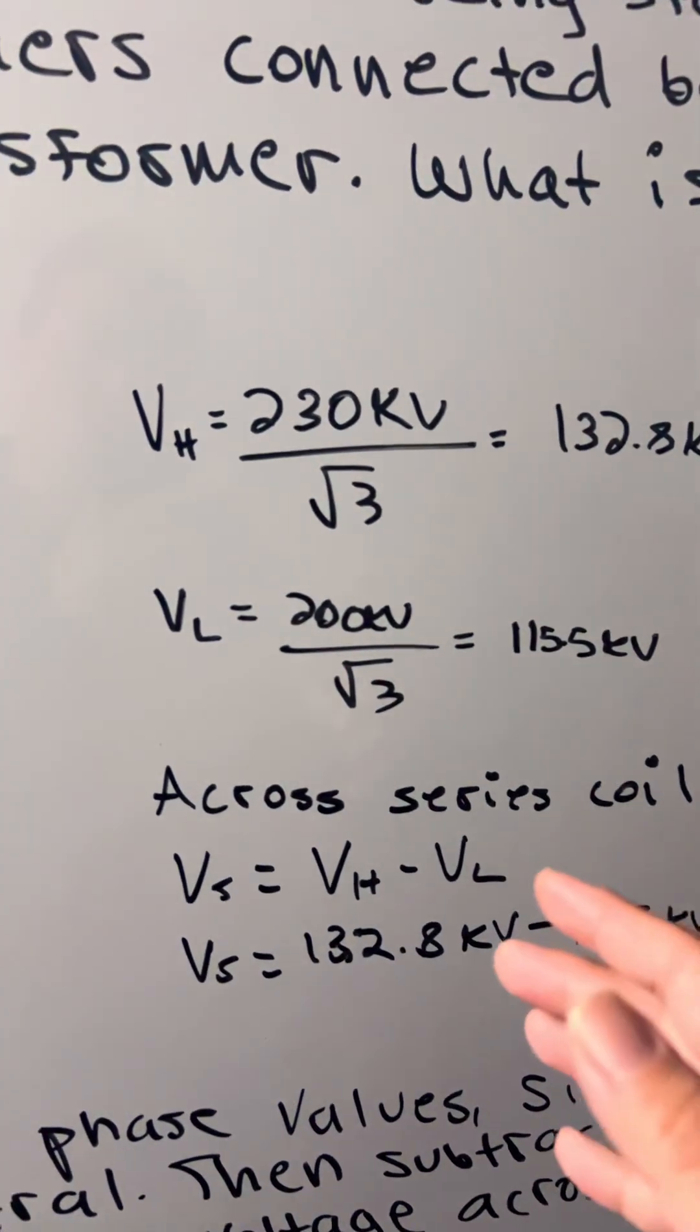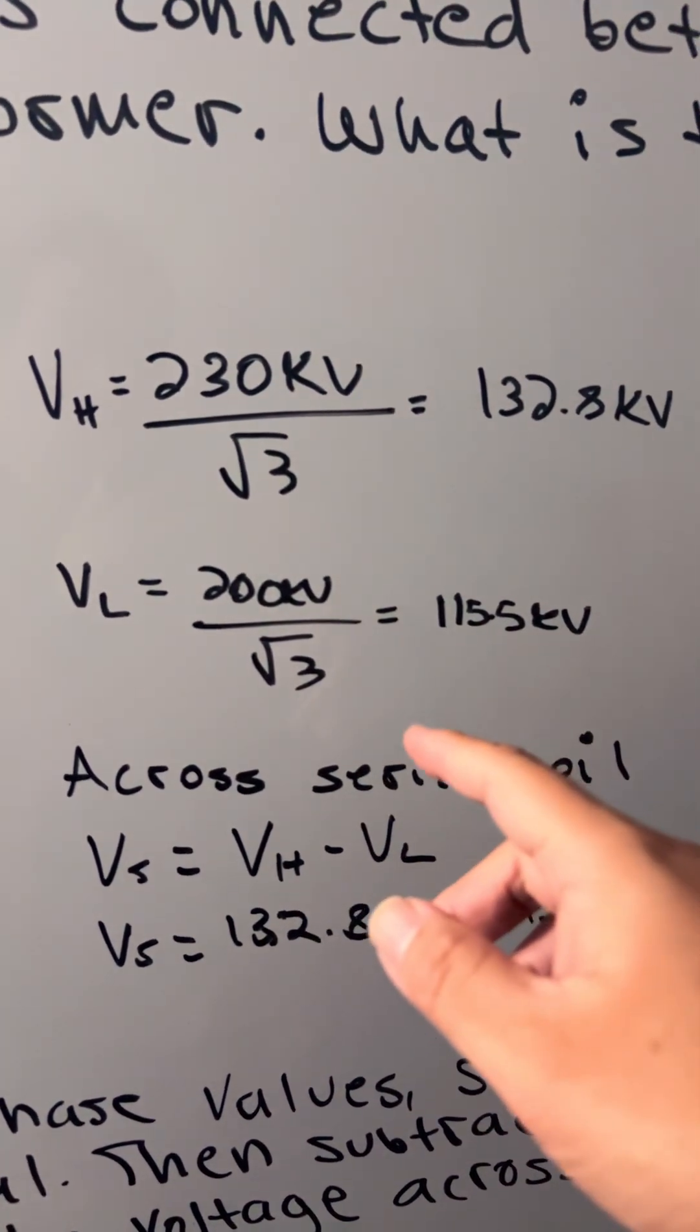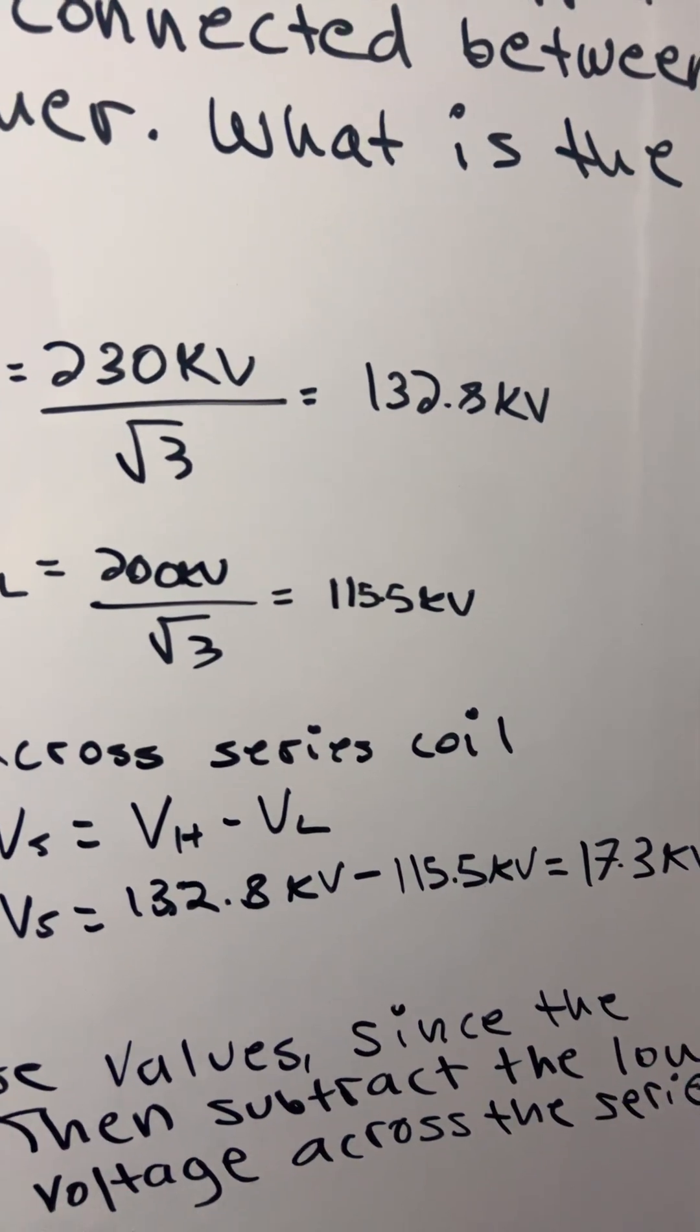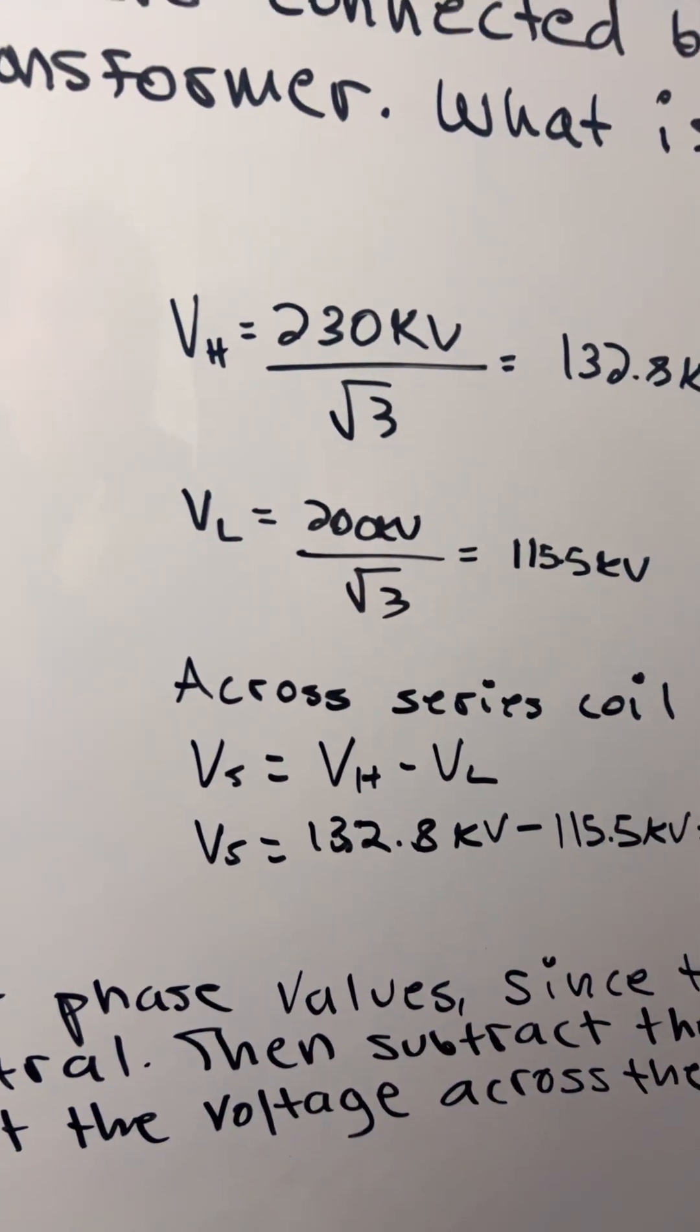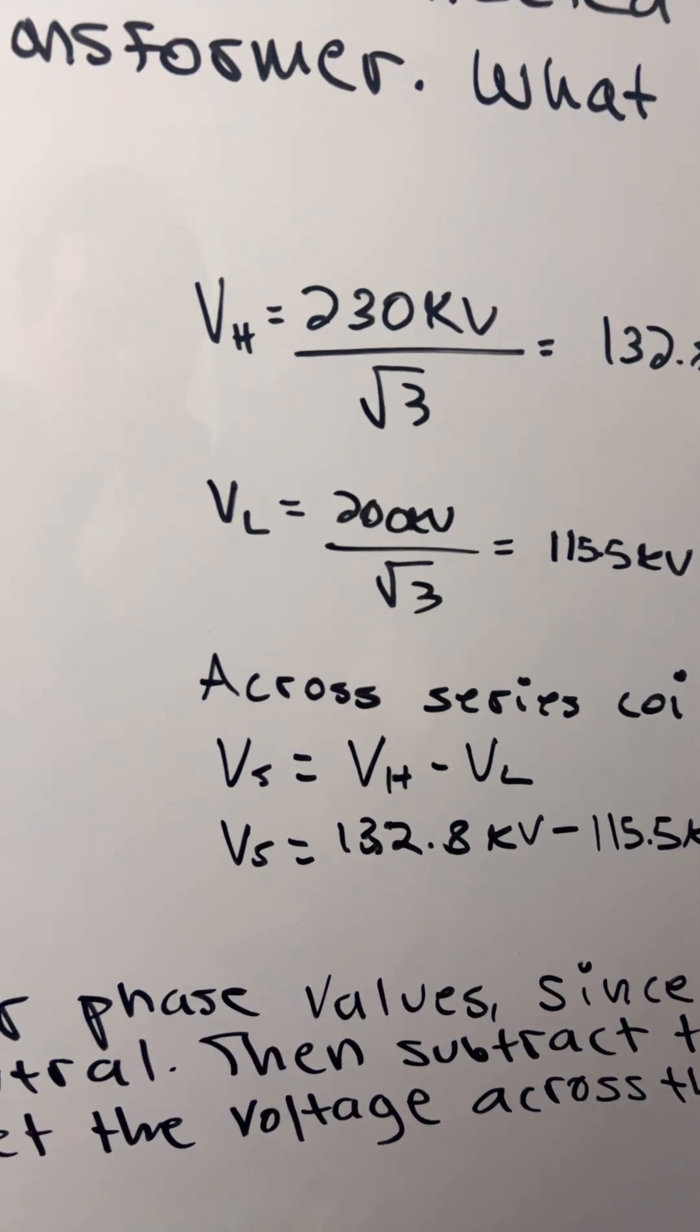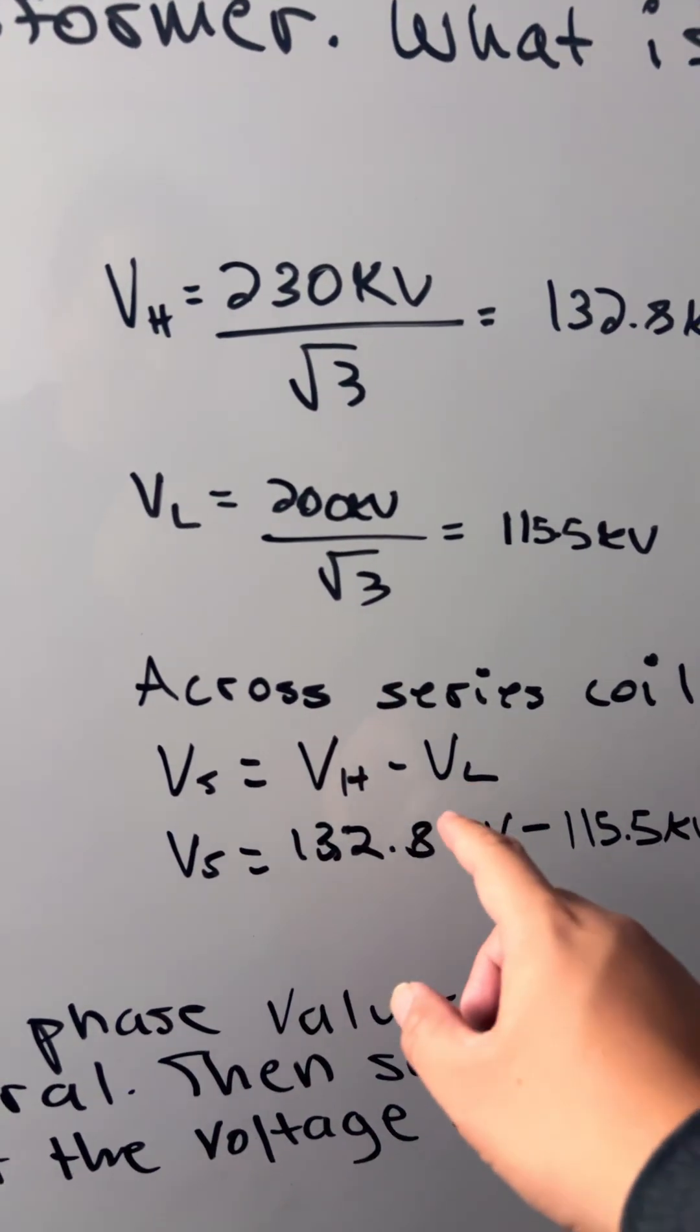Then we're going to do the same thing for the lower voltage, so 200 kV divided by square root of 3 equals 115.5 kV. The last step is to find the series coil voltage, so Vs equals Vh minus Vl.